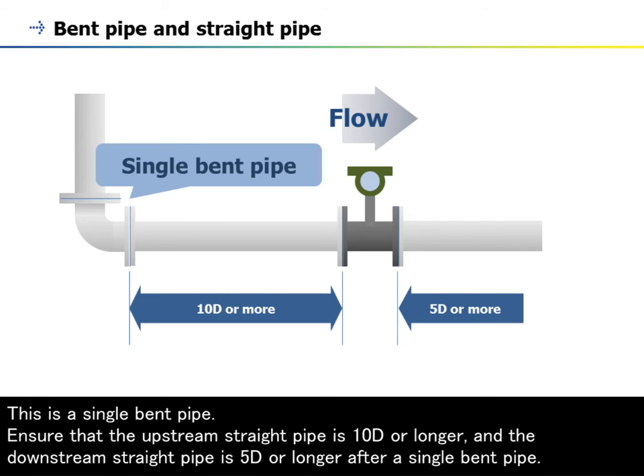This is a single bent pipe. Ensure that the upstream straight pipe is 10D or longer, and the downstream straight pipe is 5D or longer after a single bent pipe.